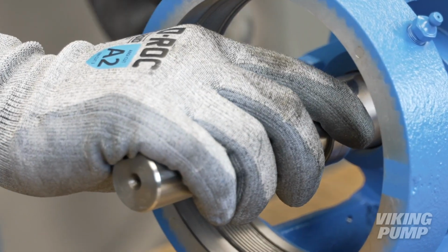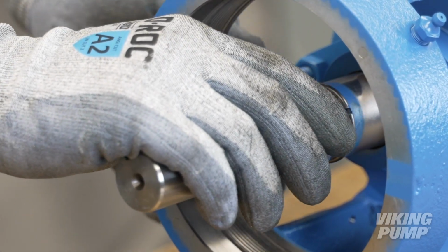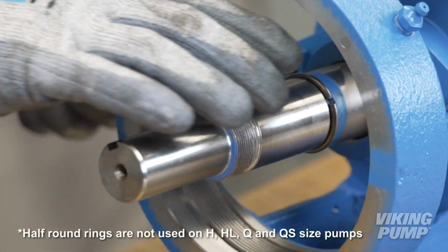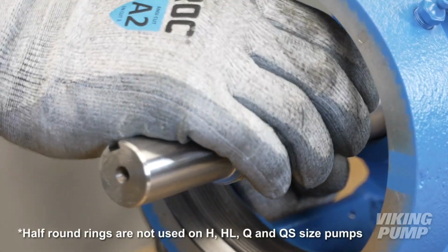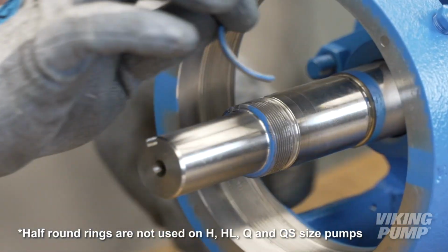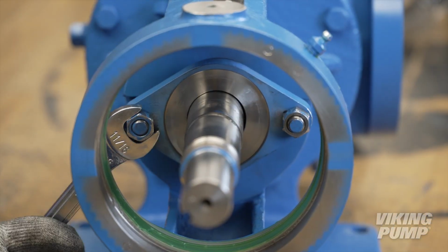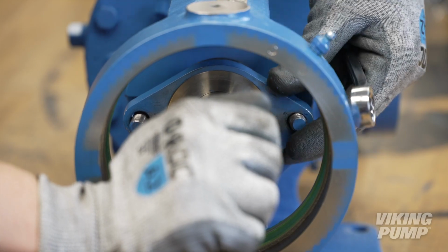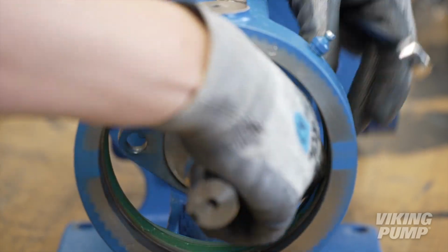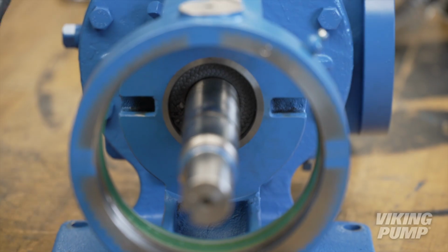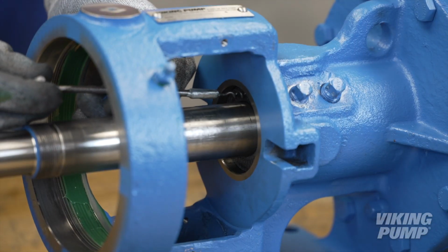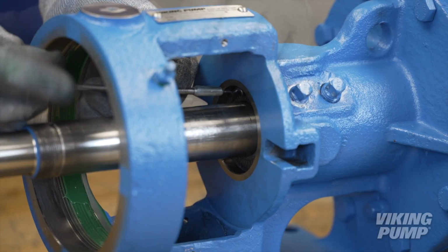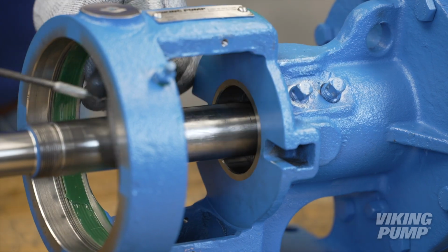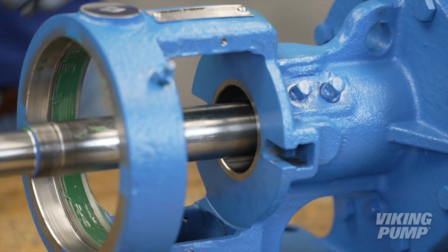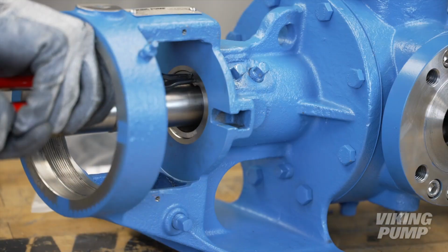Remove the bearing spacer collar. The collar may have come out with the bearing housing. Remove the half-round rings. Loosen and remove the packing gland lock nuts. Remove the packing gland. Remove the T-bolts. Using a packing hook, remove each packing ring. Remove the packing retainer washer and internal retaining ring.